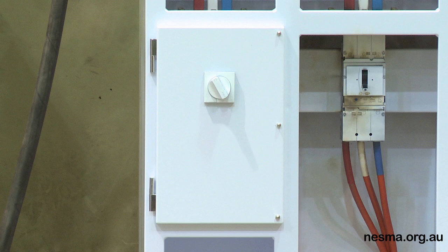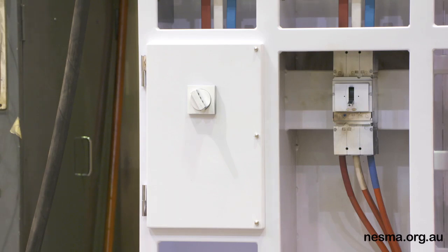The door could blow open, even though the fastenings look fairly reasonable. If it were a tongue arrangement for closing, I would think that there was a high possibility of the door flying open during the test. Once we're in a bolted arrangement, there's more likelihood of the bolts keeping the door closed. But what will happen is there's a lot more pressure on the hinge side, for example. It's just a pintle hinge, which we could see shearing of the pin on that side. But for all intents and purposes, the pressurisation of the unit between a standard arc fault test and a normal operation of the circuit breaker doesn't vary too much, and we get the same sort of reaction between.